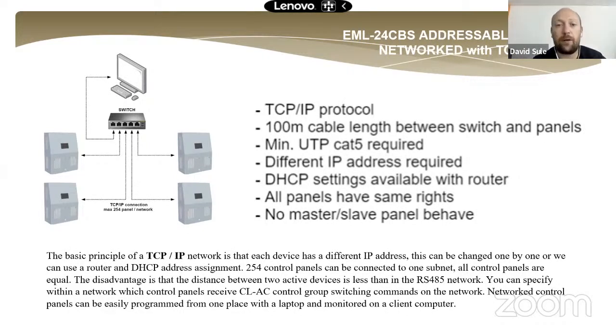So the RS-485 network and the TCP/IP network are both available for the panels. You can choose between these two types of communication. But I think the TCP/IP network is easier. You can connect more than 32 panels, maximum 254 panels, to each other. It's easy to connect any panel to your laptop. You can program all panels in the same session in the RS-485 network and the TCP/IP network too.